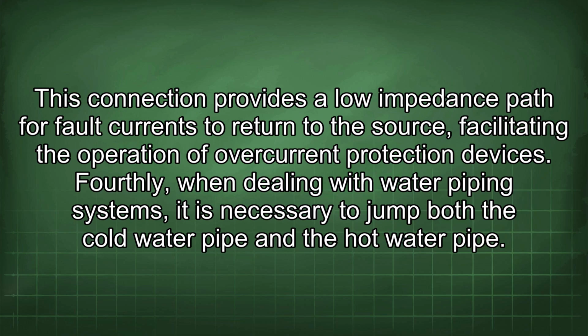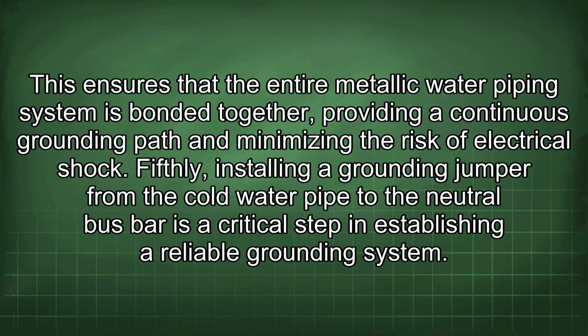Fourthly, when dealing with water piping systems, it is necessary to jump both the cold water pipe and the hot water pipe. This ensures that the entire metallic water piping system is bonded together, providing a continuous grounding path and minimizing the risk of electrical shock.